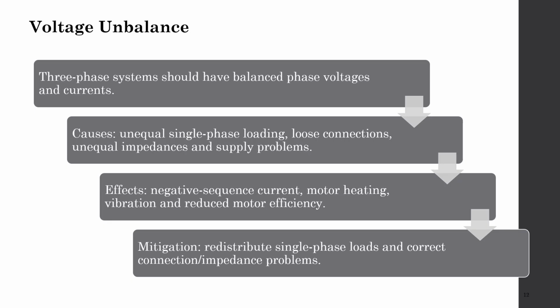Voltage unbalance. A three-phase system should have balanced phase voltages and currents. Unbalance happens because of unequal single-phase loading, loose connection, unequal impedance, and supply problems. This affects negative sequence current, motor heating, vibration, and reduced motor efficiency. To mitigate this, we redistribute single phase loads and correct connection and impedance problems.